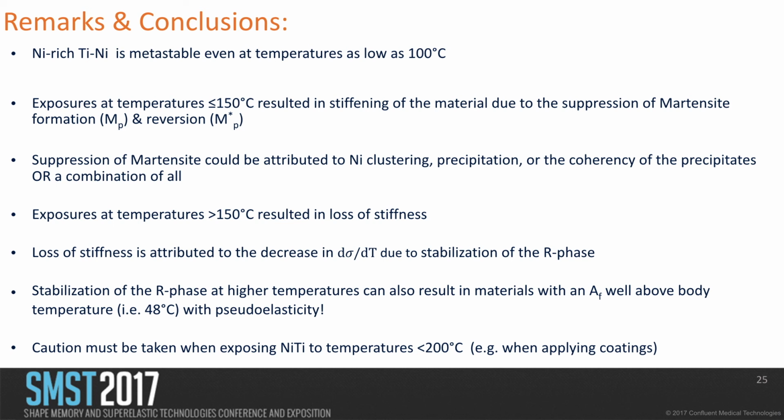We have a lot of material in inventory, and a lot of that material has been in inventory for quite some time. Would it make sense to retest some of the wire or tube after multiple years? And would you expect to see a difference there? Well, theoretically, if we had it on the shelf for 100,000 years or something, maybe. But again, it's a good point. We don't know if it's under stress or crimped, what's going to happen to it at that temperature. So yes, I would test it, but theoretically it shouldn't move much.